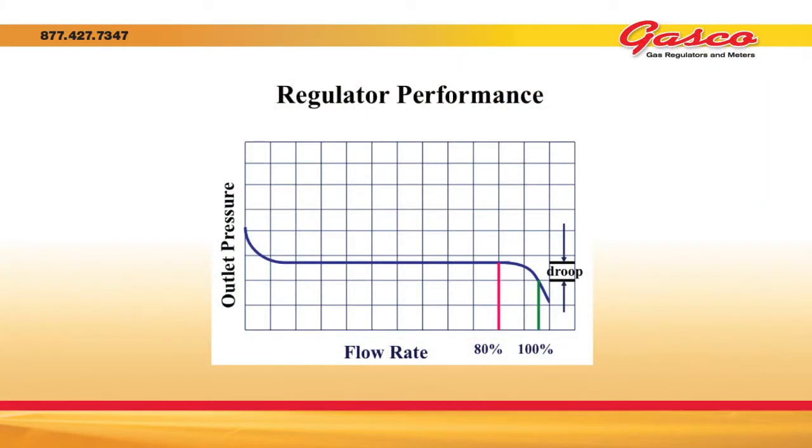A gas regulator works exactly the same way. As you approach the upper end capability of the regulator, it will start to sacrifice pressure to maintain flow rate. However, a regulator has some inherent design characteristics that do not produce the ideal curve. Droop is most evident and has the most dramatic effect in the last 20% of the flow range of the regulator, as demonstrated by the performance curve.